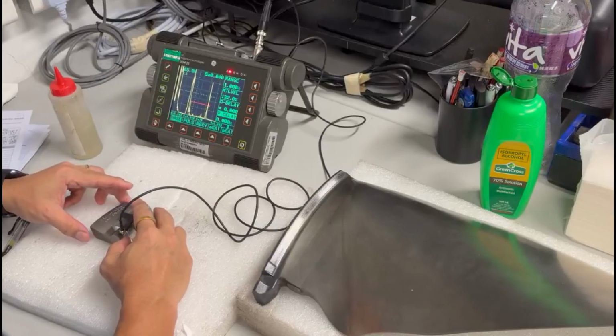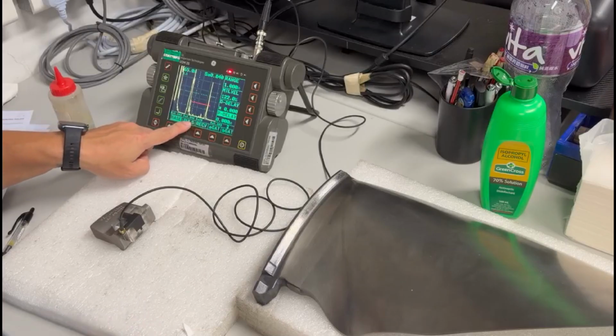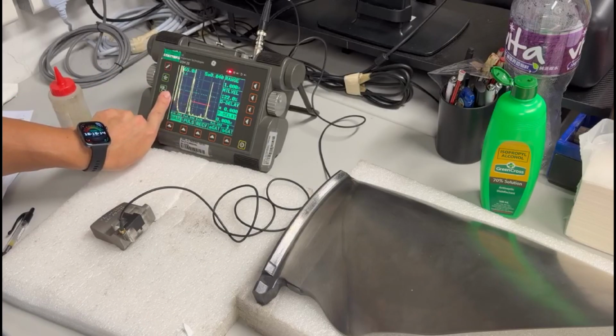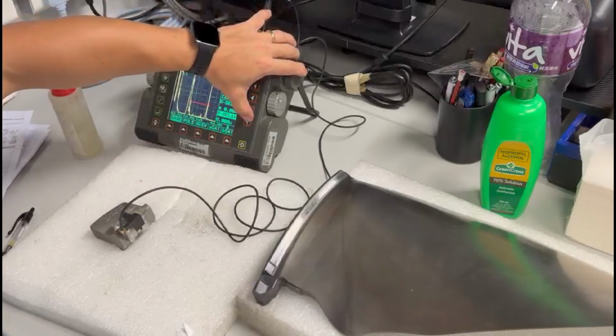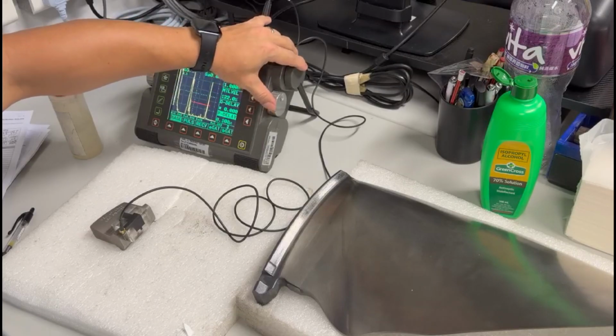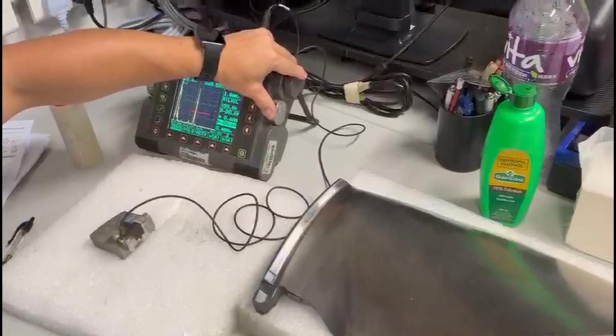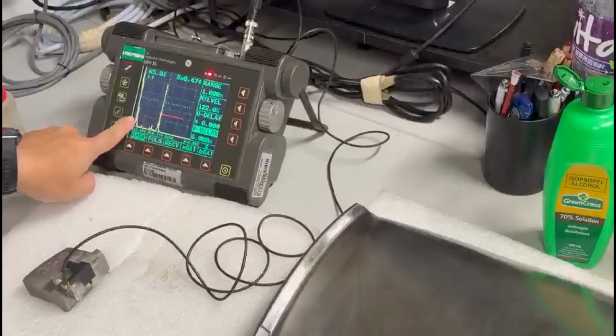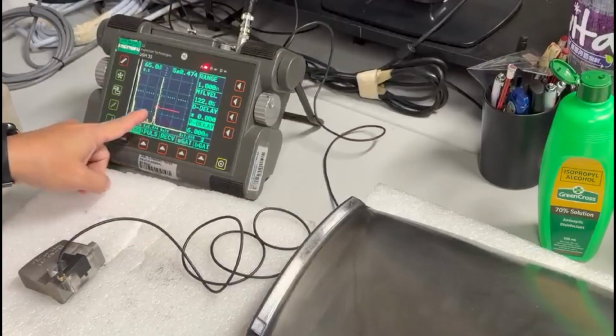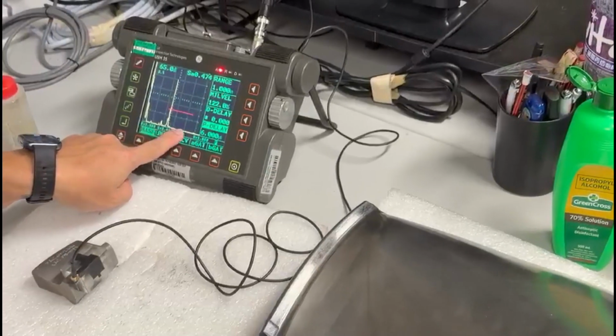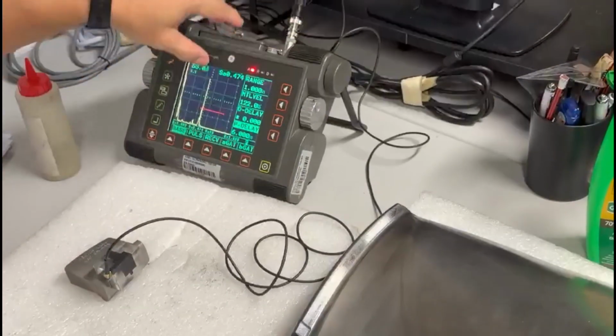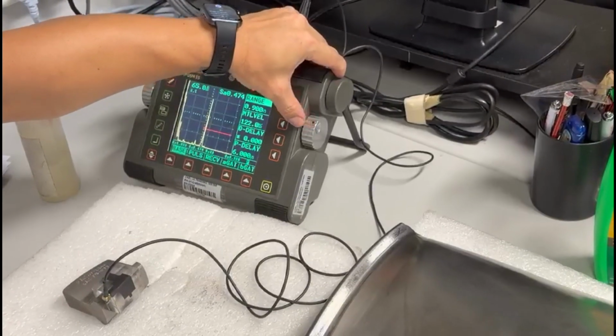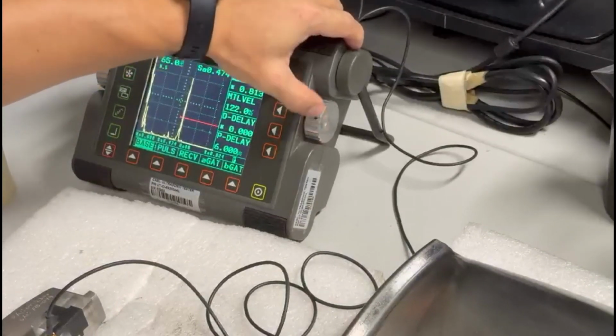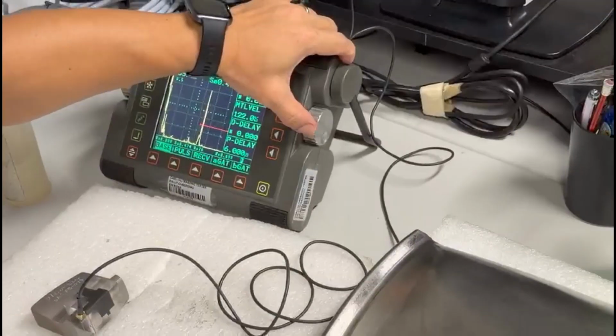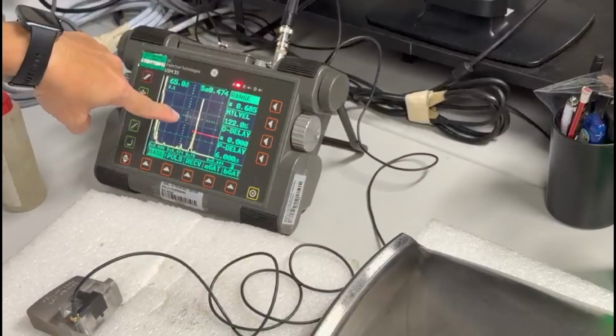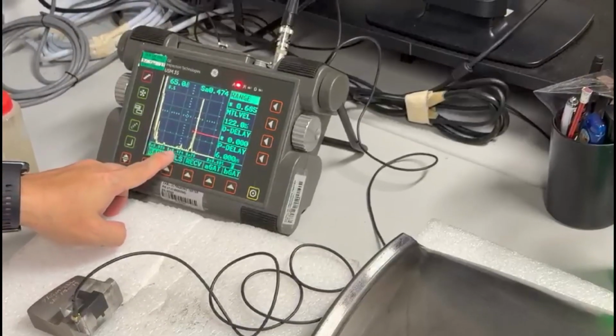Alright, 80%. Then, the next step, we need to move this wedge signal to 0. To do that, we need to adjust our probe delay. Probe delay. Move that to 0. That's it. Probe delay to 0. Then we need to move our side drill hole signal to 7. So this is 6, 8, 10. So it's between 6 and 8. We do that by adjusting our range. Alright. 6 to 7.